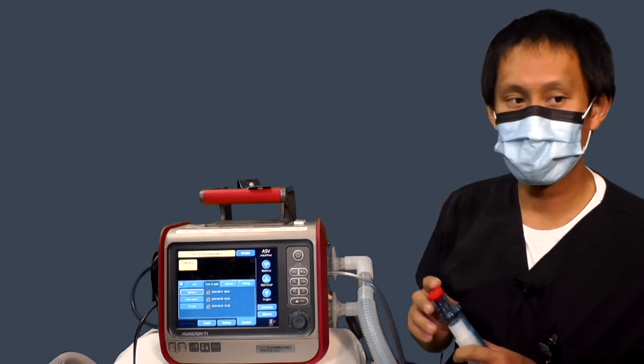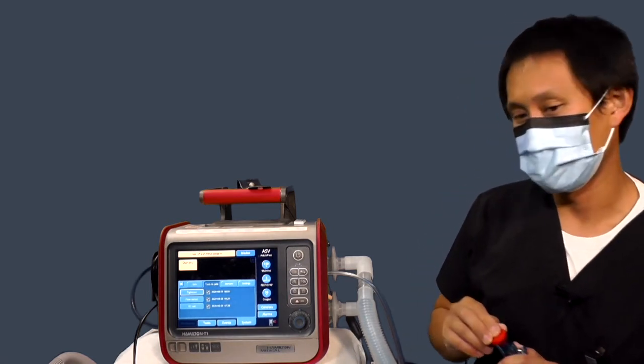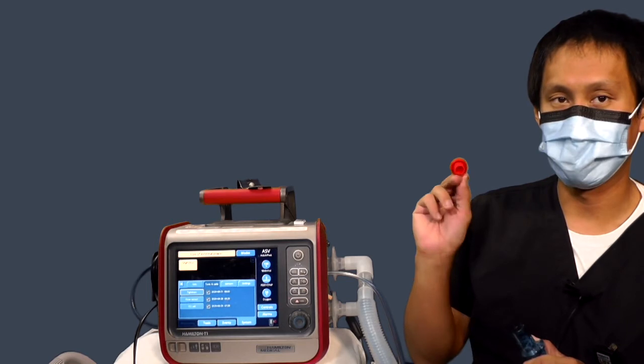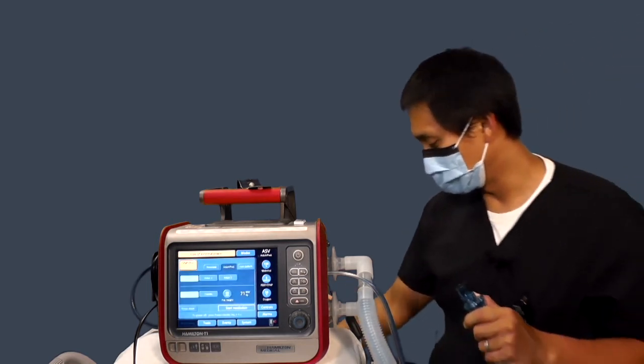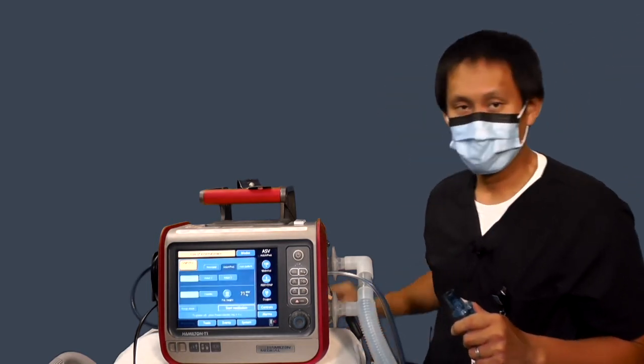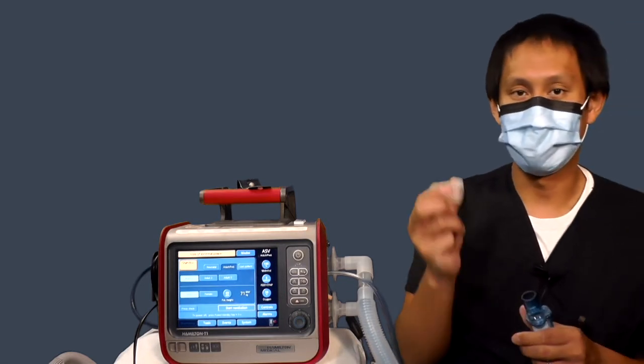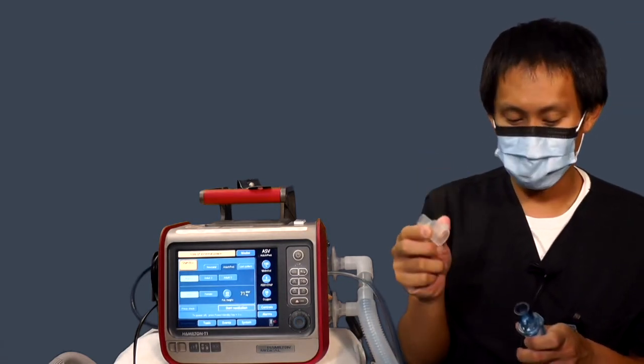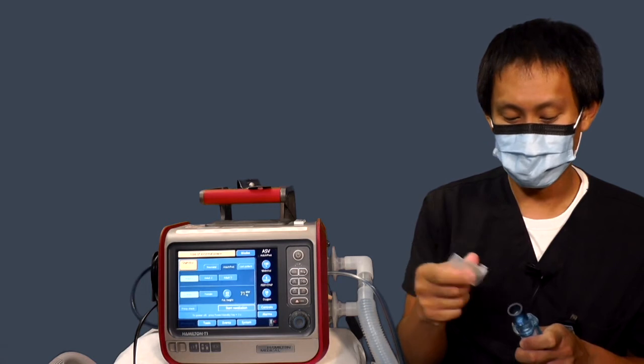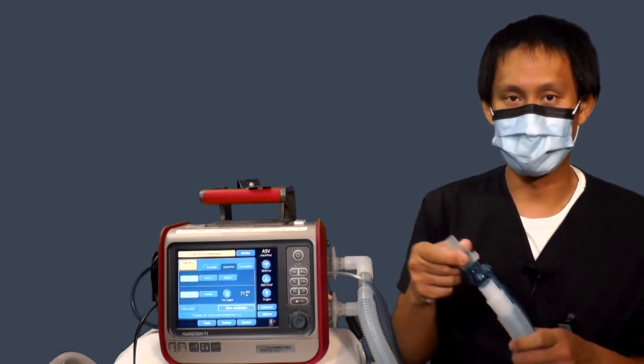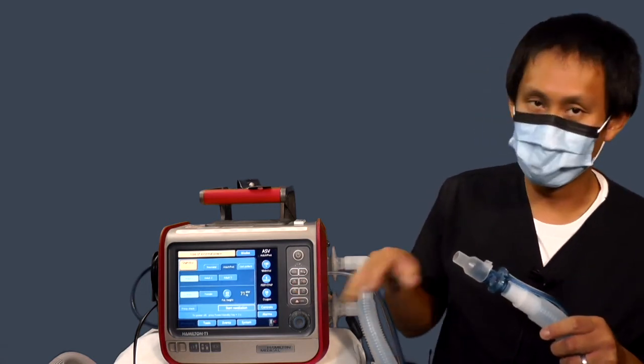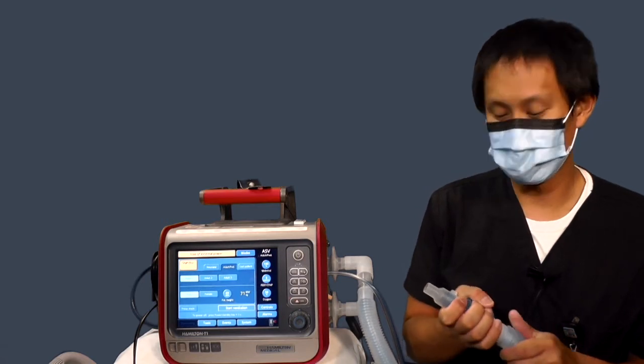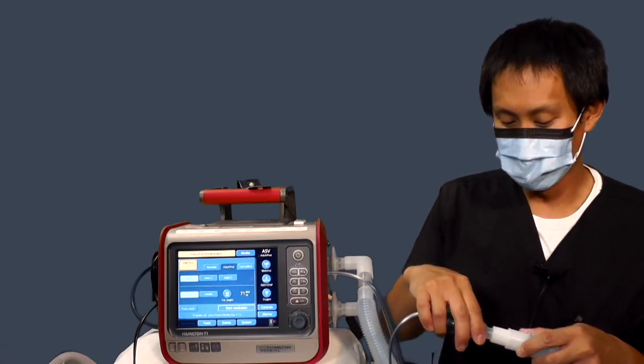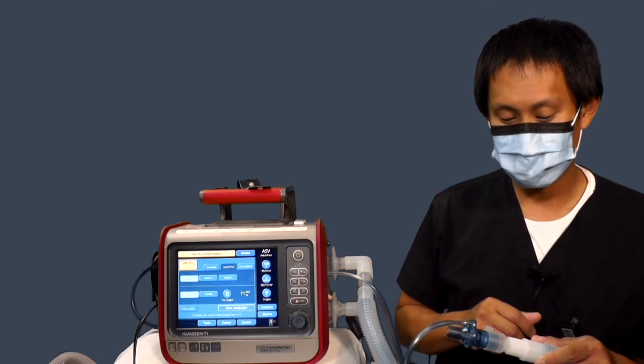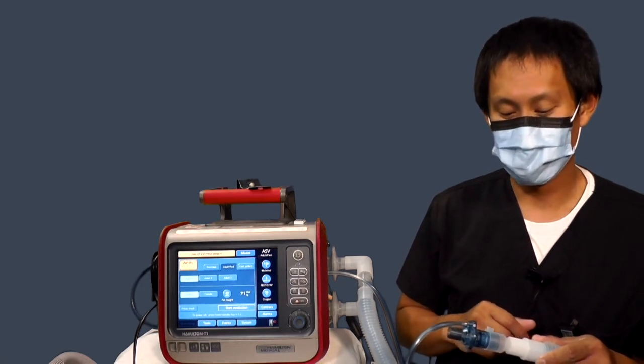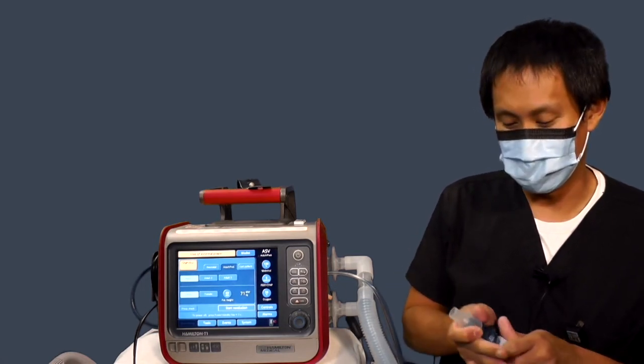So we'll move on to the flow sensor test. For the flow sensor test, you do not need the cap, so you can discard the cap. If you still have your adapter from the kit, this is where it comes in handy. So you're going to stick it on the end of the flow sensor, like so. When the message tells you to turn the flow sensor around, you're going to flip it around, and it fits snugly into the circuit.